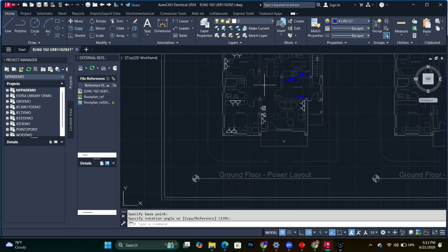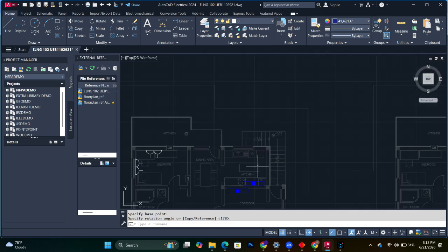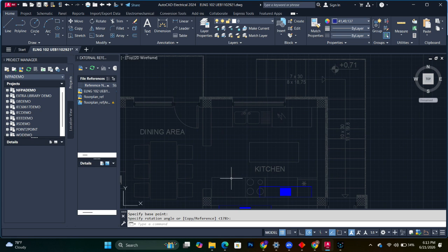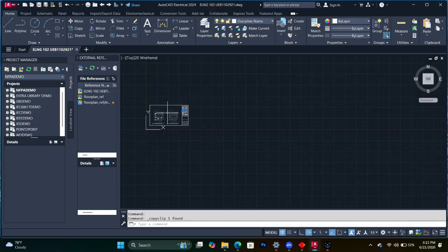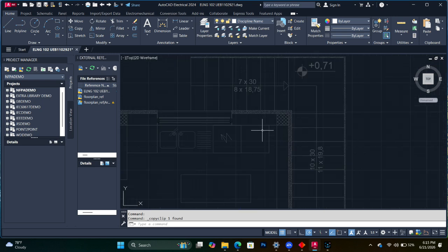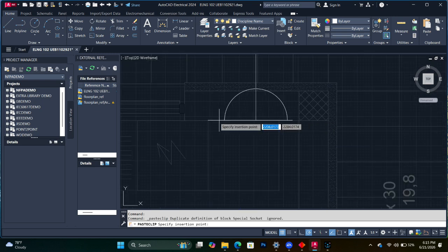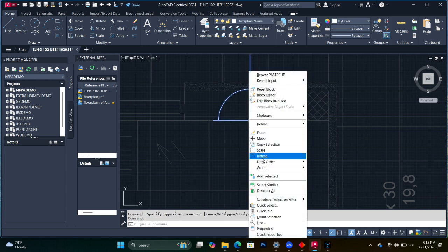Now the kitchen. This is the most important power zone in any residential layout. We already placed DBB and DBC here. Now we add the load points, find the cooker unit in the legend, copy it. This is a dedicated high load connection point, your oven, hob or electric range. It gets its own circuit from DBB. Paste it on the back wall of the kitchen, exactly where the cooker will sit.